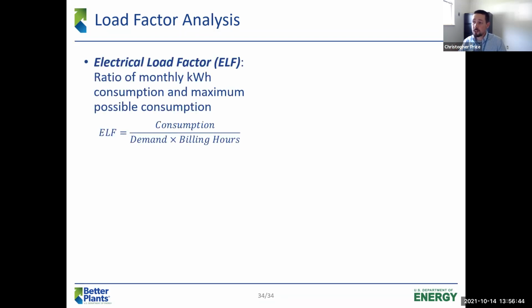Electrical load factor is a ratio of monthly kilowatt hour consumption to your theoretical maximum energy consumption. You take your billed demand, which is your peak 15 minutes of energy consumption, and multiply it by the number of hours in the month. That gives an estimate of how often your facility ran at its absolute peak energy consumption. Unless your facility uses a constant amount of energy, it's going to be fairly low.